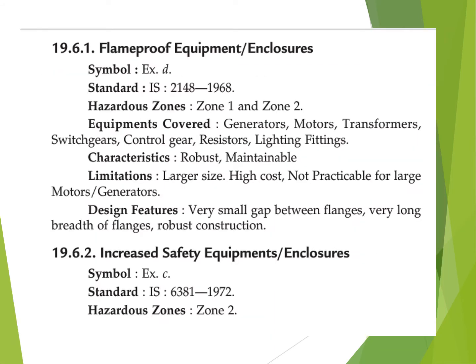Type D, that is flame-proof equipment, can be used for zone 1 and zone 2. Here the equipment covered includes generators, motors, and transformers. All the lighting fittings and so on can be covered with this flame-proof equipment, because generators and motors can produce a spark or arc. If a motor is used in zone 1 and zone 2, it should be flame-proof apparatus.